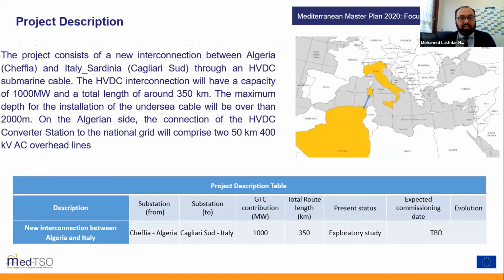The project will have a length of about 350 kilometers of submarine cable with sea depth higher than 2,000 meters. Also, in order to connect the HVDC system to the national grid, we need two 400 kV overhead lines in AC system with a total length of 100 kilometers.